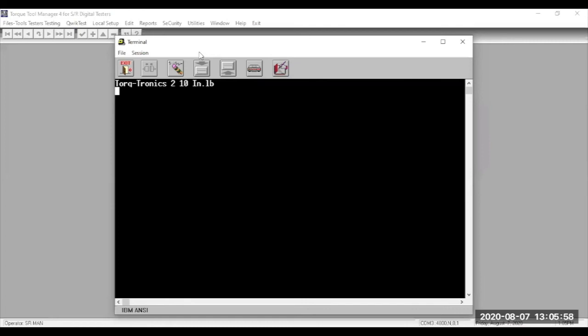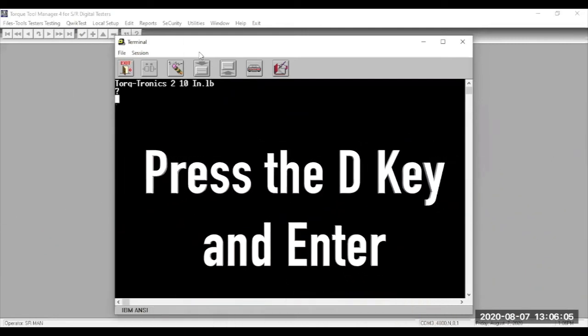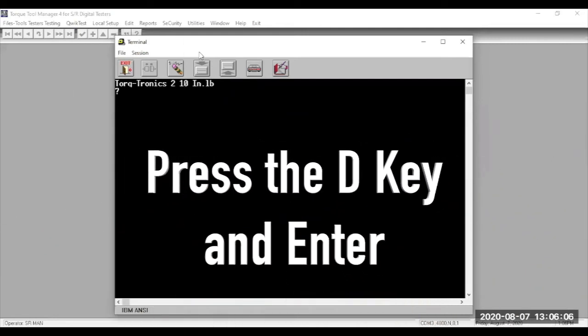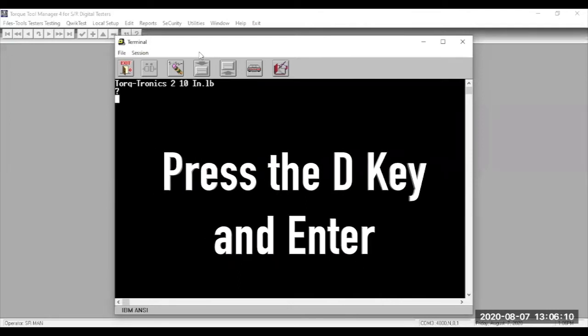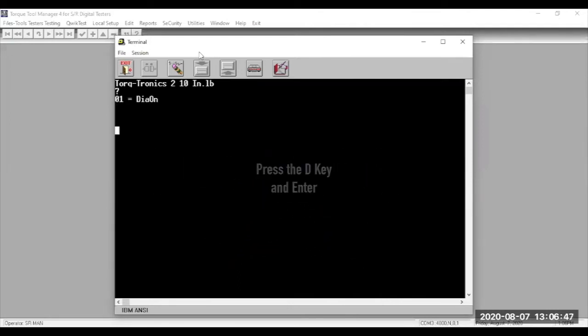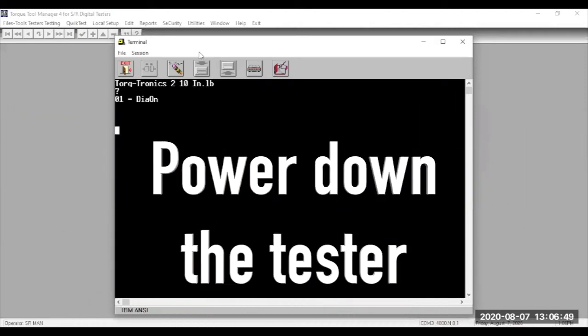Note, for this video, I don't have a unit that's over-torqued, so you won't see Z appear on the terminal display. Once the LED stops flashing, press the D key again. Press Enter. This closes the diagnostic program.